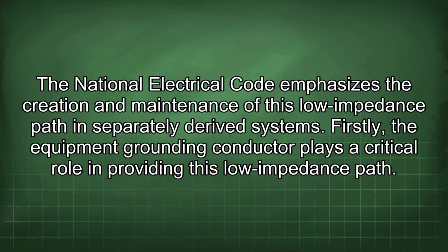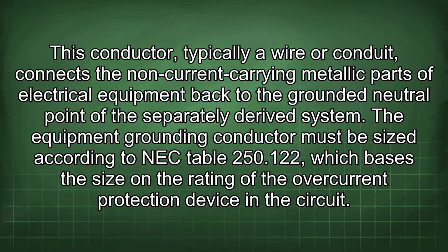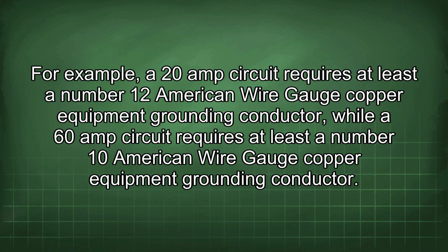Firstly, the equipment grounding conductor plays a critical role in providing this low impedance path. This conductor, typically a wire or conduit, connects the non-current carrying metallic parts of electrical equipment back to the grounded neutral point of the separately derived system. The equipment grounding conductor must be sized according to NEC Table 250.122, which bases the size on the rating of the overcurrent protection device in the circuit. For example, a 20 amp circuit requires at least a number 12 American wire gauge copper equipment grounding conductor, while a 60 amp circuit requires at least a number 10 American wire gauge copper equipment grounding conductor.